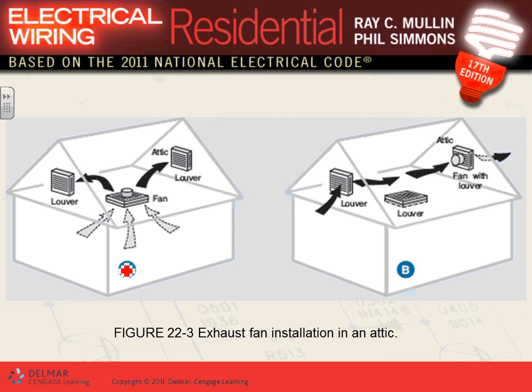Our intention, guys, when you have the fan, is you need to go, here's my fan. You need to power it. If you have a fan in the attic, the best application: here's my fan, I can put a 20 amp circuit here or a 15 amp circuit. Let's say a 15 amp circuit. Most of them are small. You have a dedicated 15 amp circuit, and you have some controller to control the temperature. That's it.